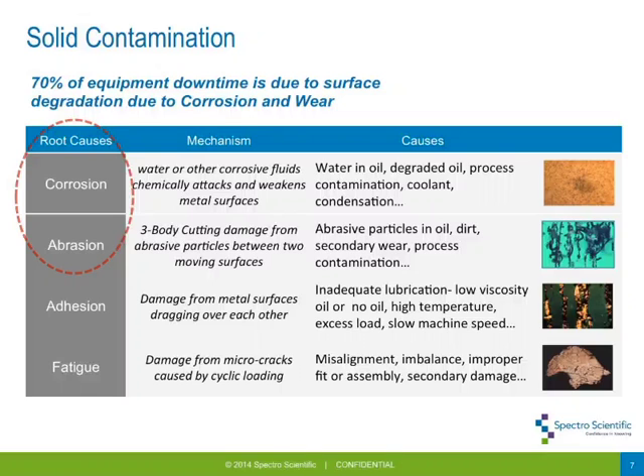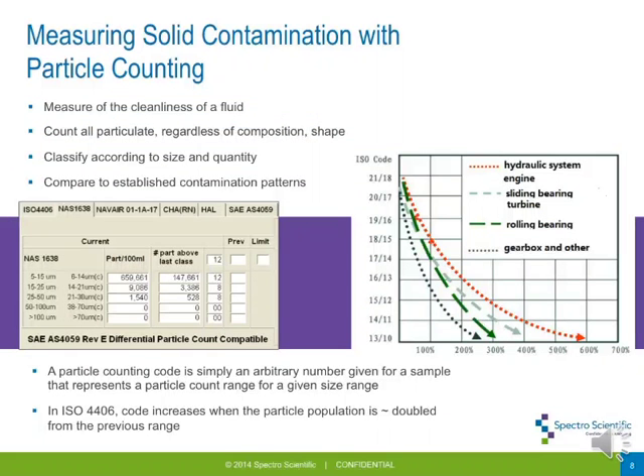If you look around the industry, many OEMs and service companies, major mining equipment customers, and turbine companies operate contamination control programs focused on controlling the level of solid contamination getting into the system. One of the overarching measurement approaches when talking about solid contamination is particle counting. Particle counting has been around for almost 40 to 50 years, originally aimed at hydraulic cleanliness. It's a measure of the overall cleanliness of a fluid — measuring all the particles regardless of composition and shape, binning them according to size and quantity.